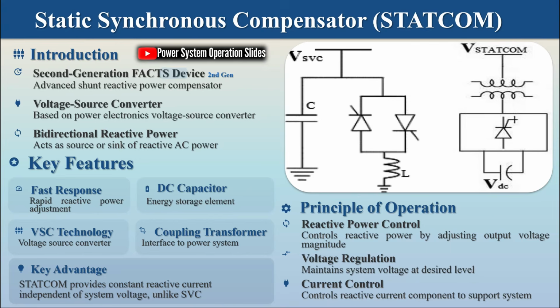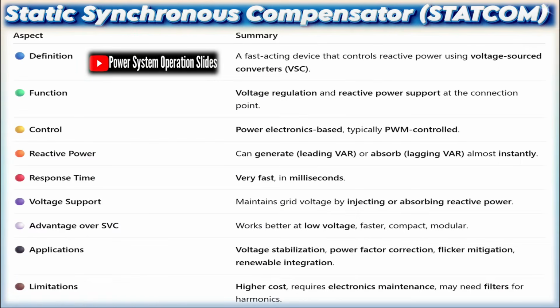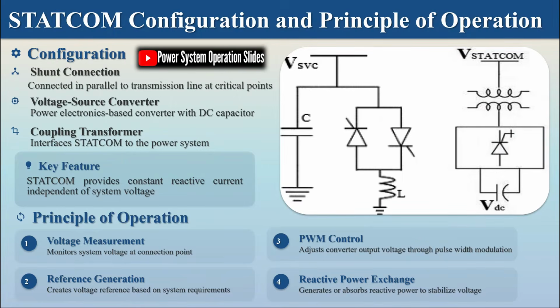From a technical perspective, STATCOMs offer several advantages over SVCs. Their faster response time enables more effective mitigation of rapid voltage fluctuations and better support during transient events. The voltage-independent reactive current capability ensures full performance during low-voltage conditions, which is critical for preventing voltage collapse. Additionally, STATCOMs typically generate higher-order harmonics that are easier to filter than the lower-order harmonics produced by SVCs. The compact design of STATCOMs also results in a smaller physical footprint, which can be advantageous in space-constrained installations.